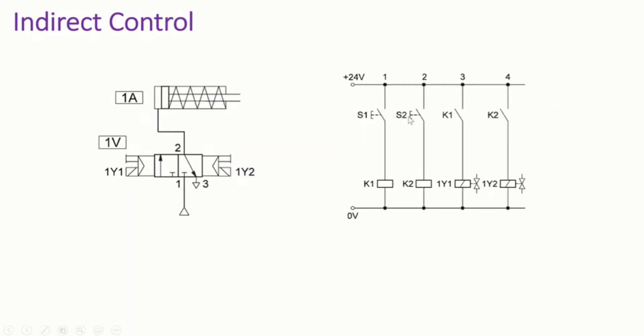When the piston reaches the fully advanced position, we turn on switch S2. From there K2 is energized, K2 closes, and we have solenoid 1Y2 energized. That electrical actuation returns the valve back to its initial position, the air is exhausted, and the piston inside the cylinder retracts. That is how indirect control works.